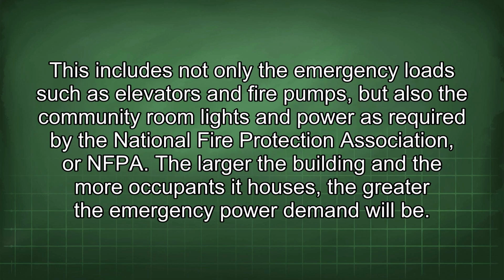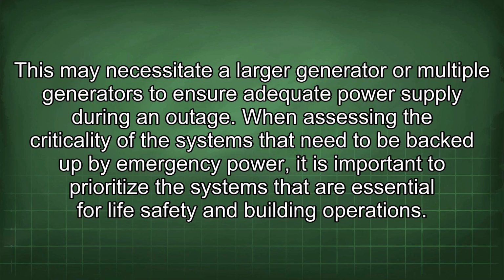This includes not only the emergency loads such as elevators and fire pumps, but also the community room lights and power as required by the National Fire Protection Association, or NFPA. The larger the building and the more occupants it houses, the greater the emergency power demand will be. This may necessitate a larger generator or multiple generators to ensure adequate power supply during an outage.